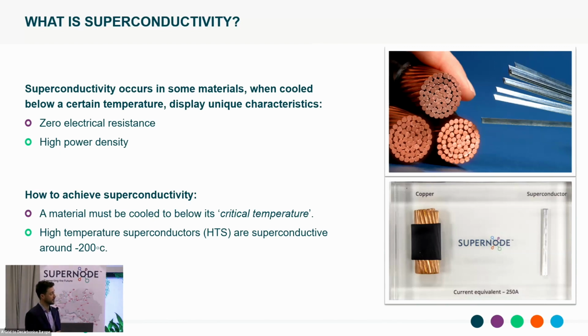We operate the cooling system using liquid nitrogen - it's very convenient, cheap, abundant, and a well understood cryogen. The key advantage in terms of power cables is that you can leverage the lack of electrical resistance or losses to have a very current dense and power dense system. That allows you to reduce the system voltage and achieve really high power capacities in a power cable.